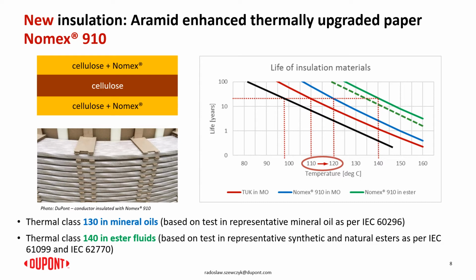So normally the cellulose, when exposed to the temperature in the operating transformer, loses its mechanical strength due to the degradation of the cellulose chain, which is the natural process. While when we add Nomex to it, the Nomex component would require much higher temperature for being degraded. Therefore, when we have that Aramid enhanced paper in the equipment, the paper would lose less mechanical strength as compared to other classic papers, and this would extend the life of the insulation system. We could also say that such paper could be exposed to higher temperatures.